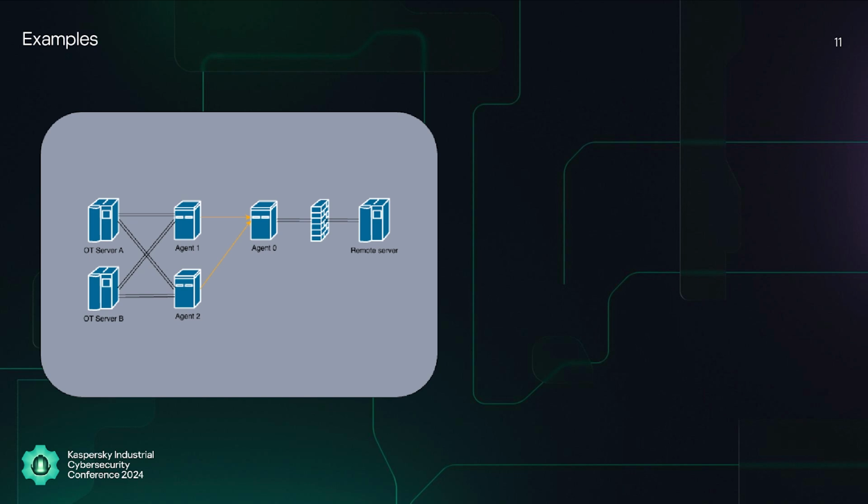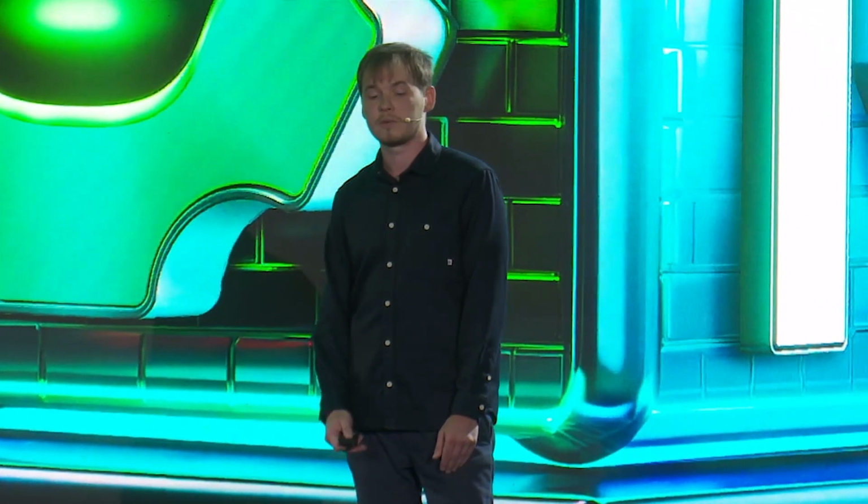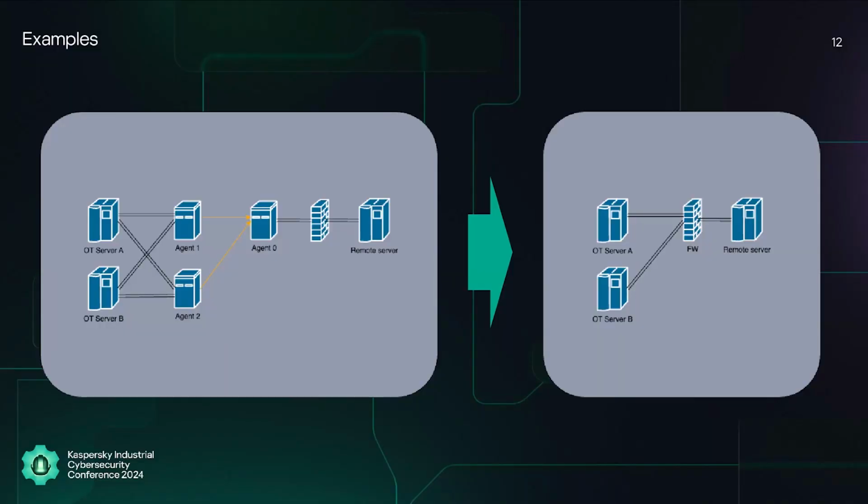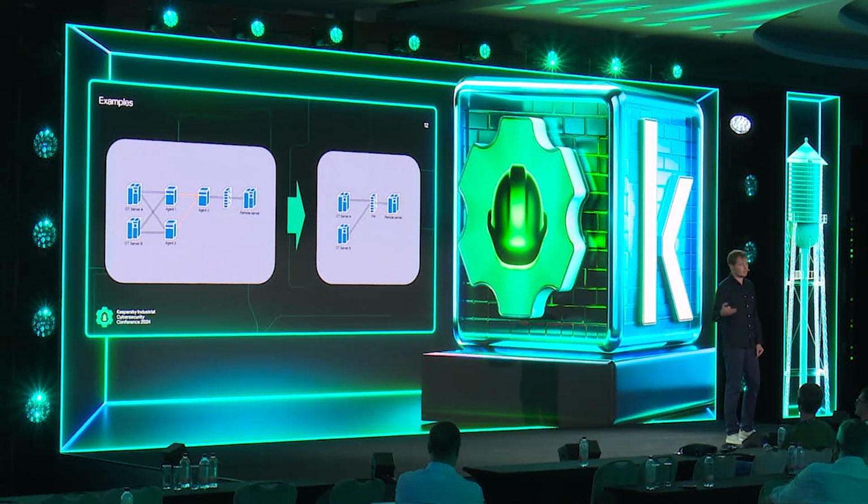But during our security analysis, in the context of pen testing, we collected information about the network, about objects, how they work, and found that some nodes have a different address. We started asking engineers what's going on, how it works. It turned out they had a separate switch where you press a button and the network reconfigures. This existed to overcome one of the problems of security, software updates and updates of antivirus databases and the like. So the network is reconfigured, and at this point, an intruder could potentially go from the corporate network to the industrial network through firewall rules.